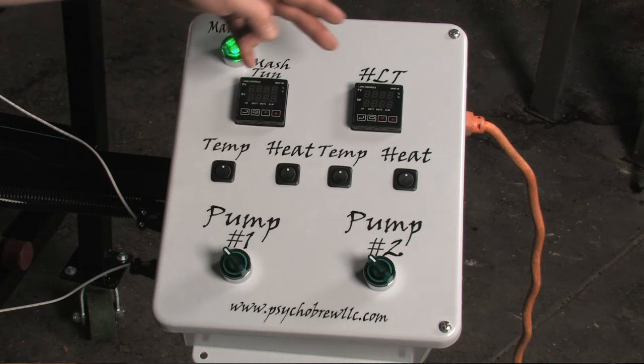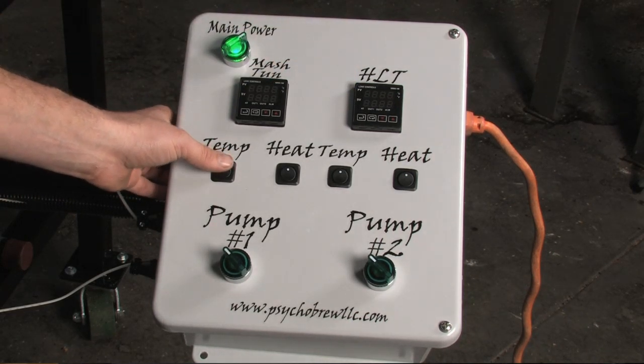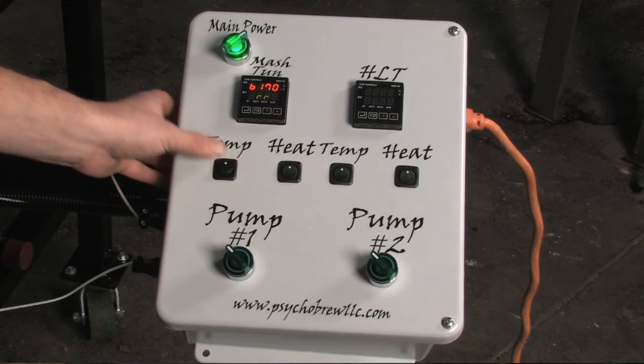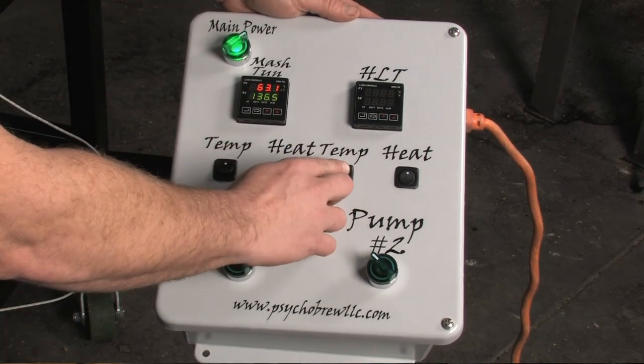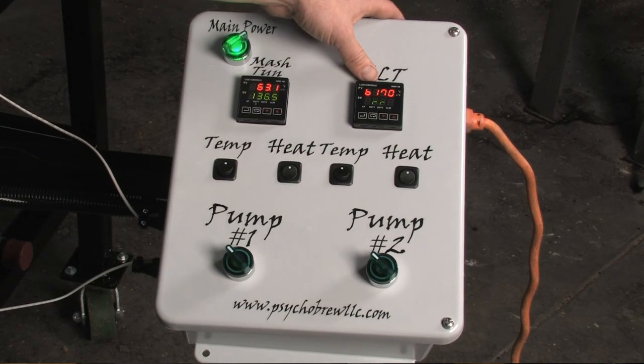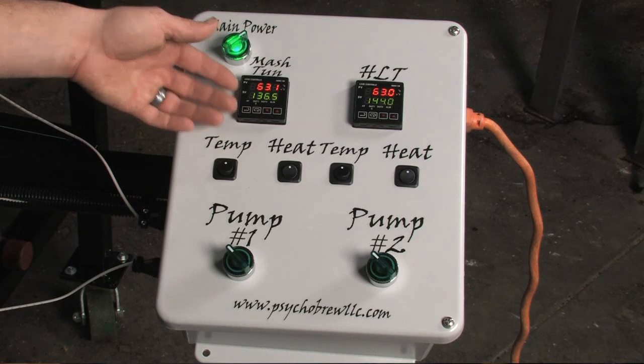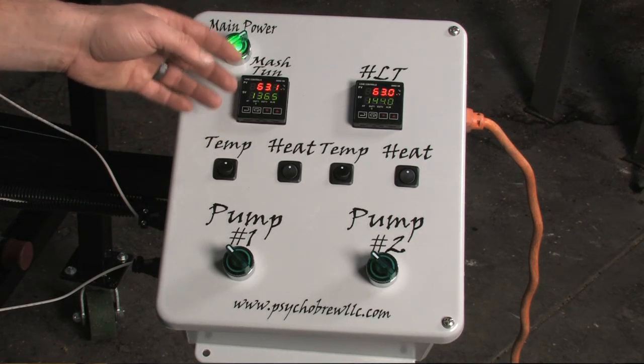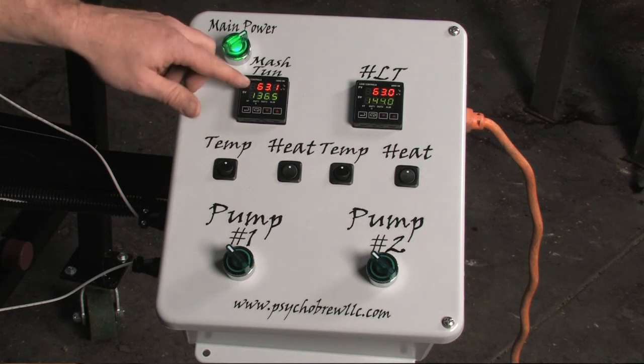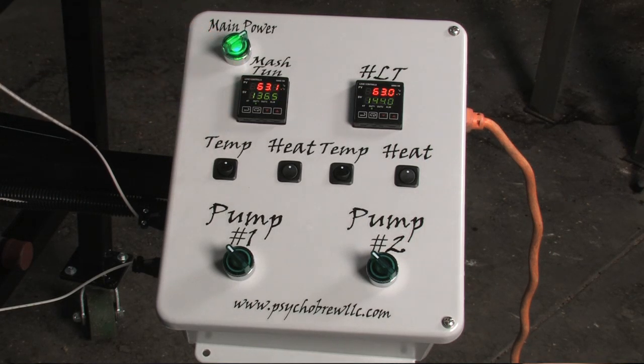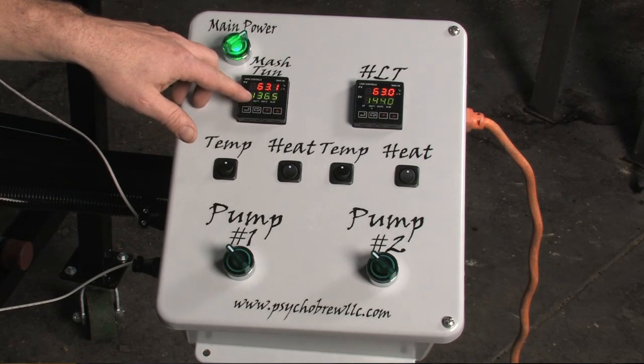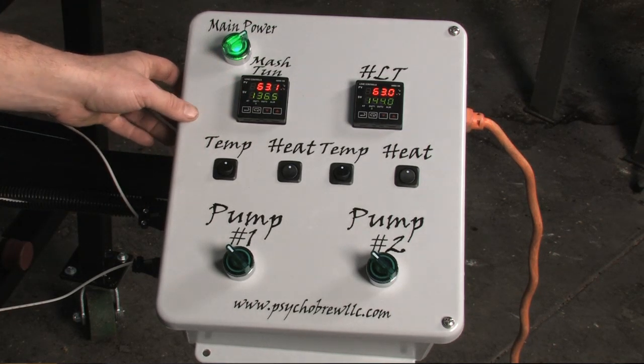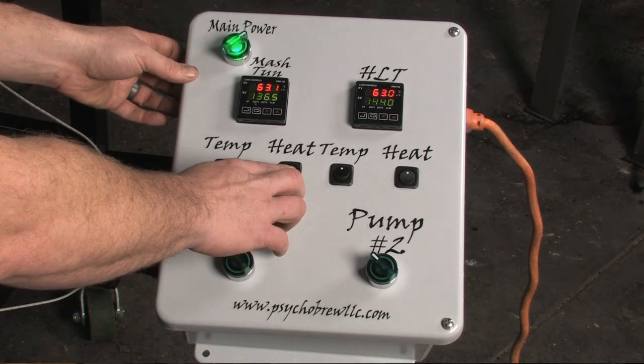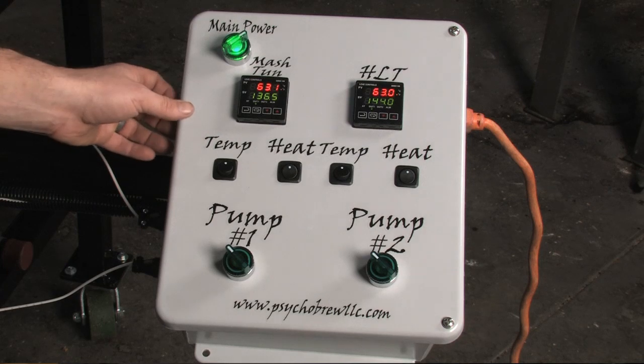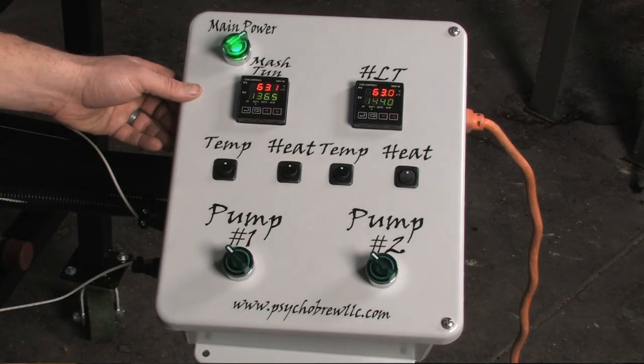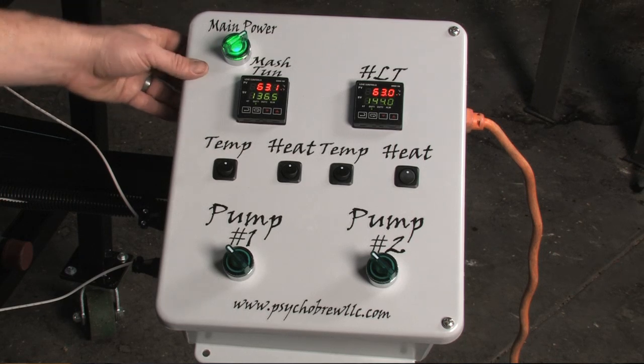Now each controller also has power. Each individual power switch here powers up the controller. Second switch also powers up that controller. You'll get some numbers on initial startup. That is the controller already starting to think and process your temperatures. The top number is your actual temperature reading from this thermistor inside the tank. The other one is your set point. Once you're ready to go, you've got a button that says heat, and that is to enable the burner. Flip that switch on, you'll have a short pause, and you'll hear some clicking. That's the igniter trying to light.